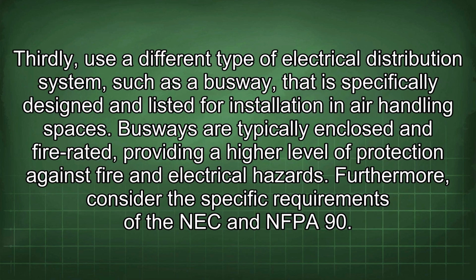Thirdly, use a different type of electrical distribution system, such as a busway, that is specifically designed and listed for installation in air handling spaces. Busways are typically enclosed and fire-rated, providing a higher level of protection against fire and electrical hazards.